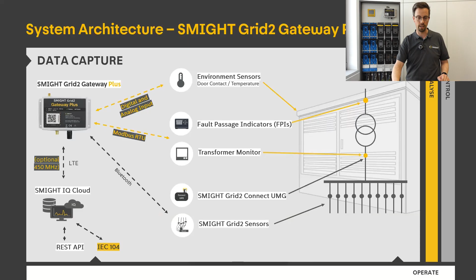With our standard gateway, you get 230 volts AC. With the Plus gateway, we have the addition of an option for 24 volt DC supply. The reason for that is that in most substations, there'll be a backup power supply, so that in case of a fault, when the substation no longer has power from the grid, it still has power to run devices such as the gateway. So we have the 24 volt DC connection on there.